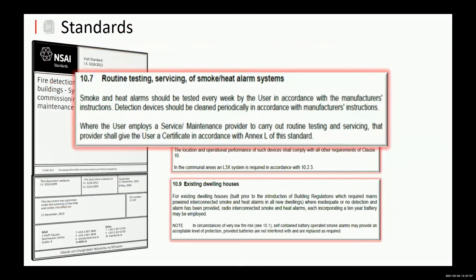Okay, we say in our standards in 10.7 that smoke alarms should be tested every week. Now we do a lot of training around the country with different groups, and we ask this question: how many people have tested their smoke alarms every week? And we don't get a reaction. So yeah, it doesn't happen. But what we do find is the more the control switches are installed with the systems themselves, people are more inclined to test the system because of the facility of the test button on the control box.